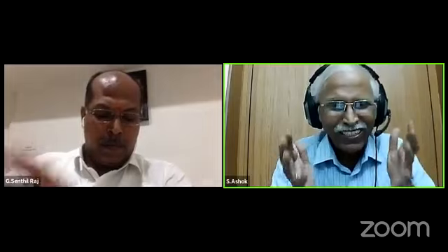Thank you. Sir, Mr. Arpan Chaya has a question. Can you suggest the best VFD supplier with low cost? Arpan Chaya, this is a webinar where I am supposed to talk only generic, totally neutral points. I cannot be branded with any VFD supplier. You go for a branded VFD supplier, which is supposed to give the best efficiency of the given blower and always at a power factor of 0.9. The VFD has to work at 0.9 power factor at any loading of the blower. That is the first point, from the electrical point of view.